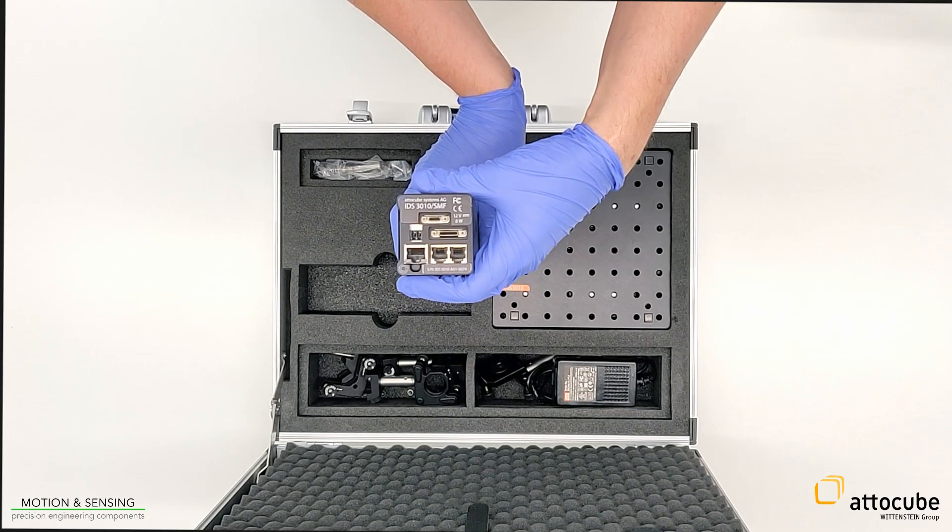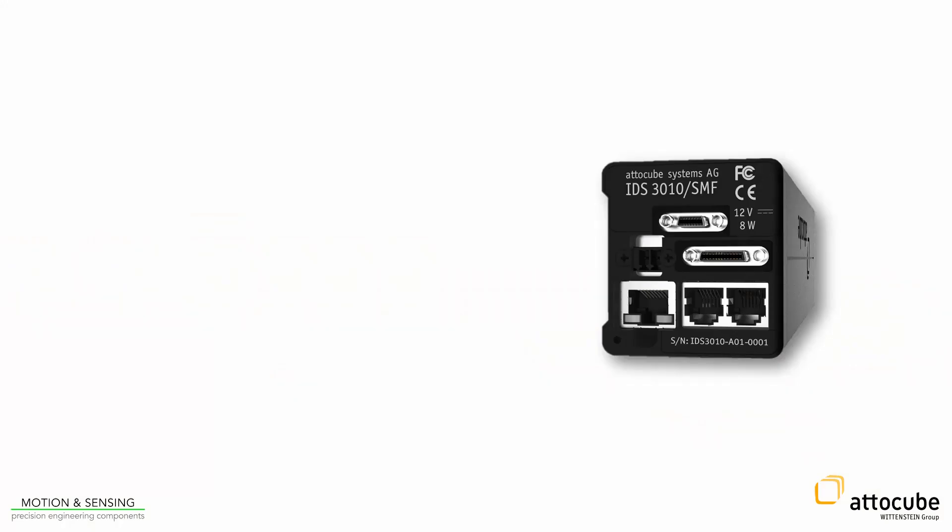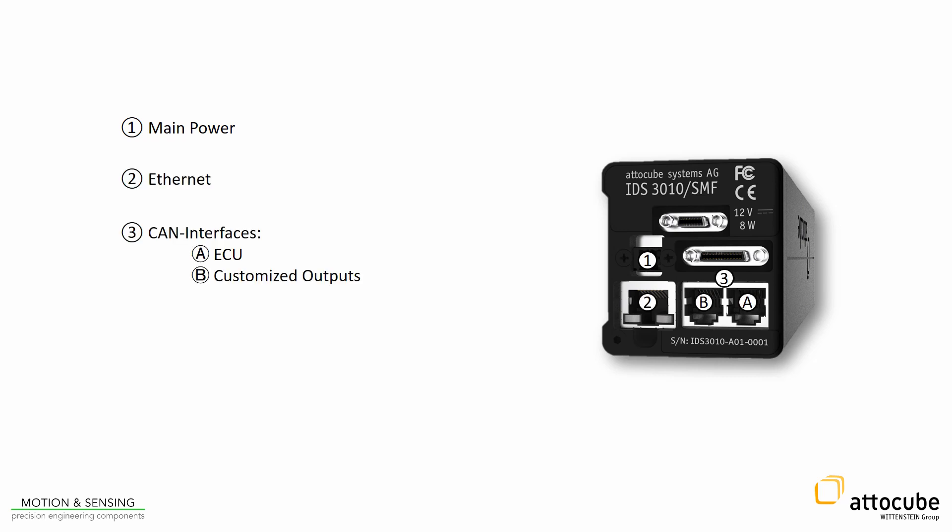The rear side of the controller includes an interface for the power, an Ethernet output, and two CAN interfaces. The right one is for connecting the environmental compensation unit, while the second one is reserved for other potential customized outputs. The rear side also includes a real-time GPIO port, which is used for the BiSS-C interface.